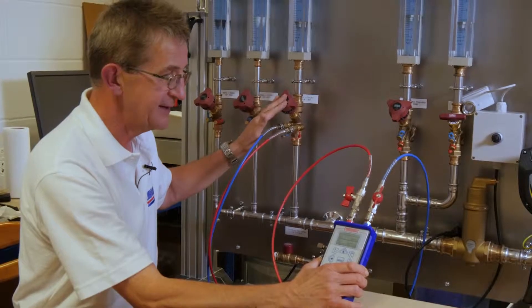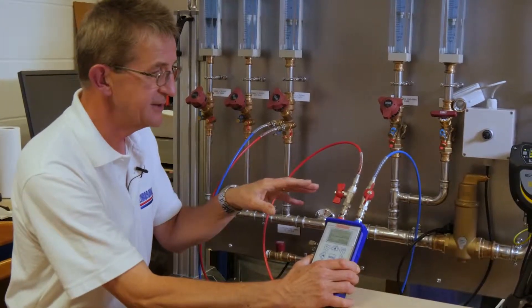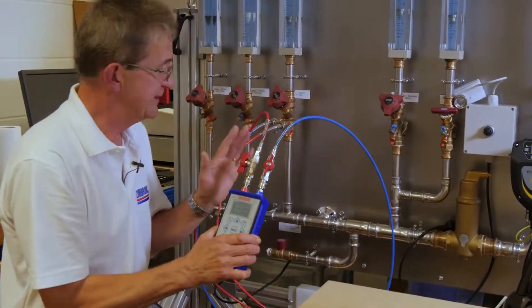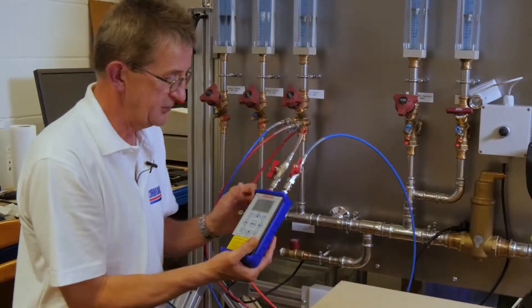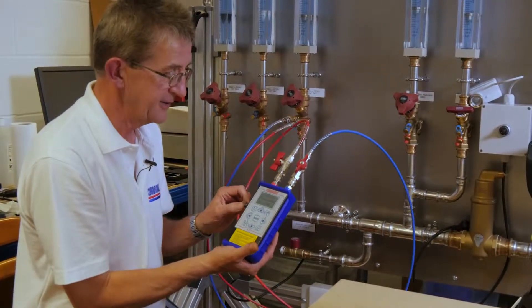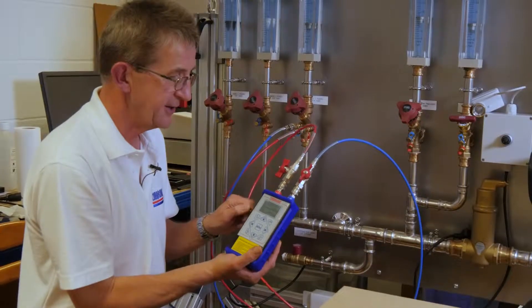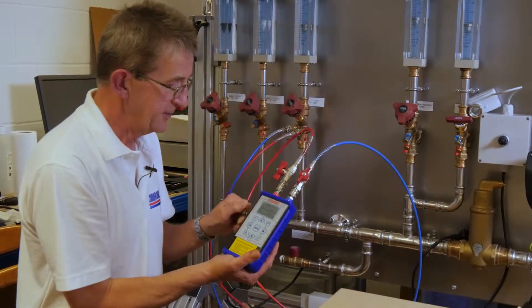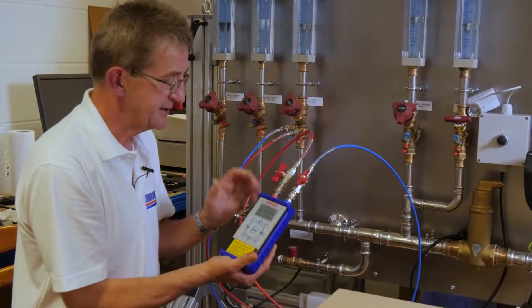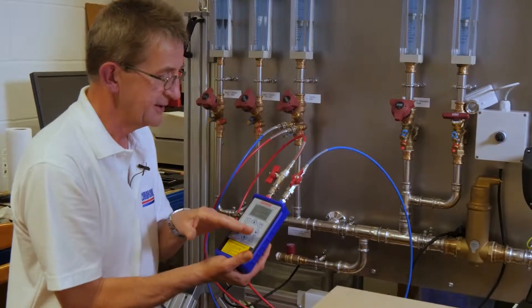In order to do that we need to safely disconnect the hoses. And before we do any disconnection of hoses always ensure that the equalizing valve on the side of the AC6 is open. If you don't open this and you disconnect the hoses there's a danger of over pressurizing the sensor.